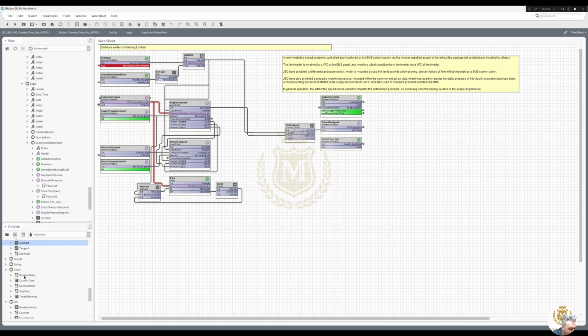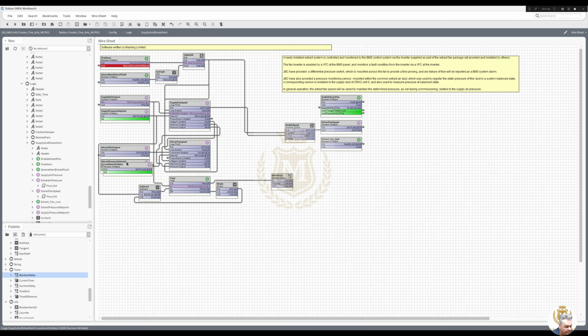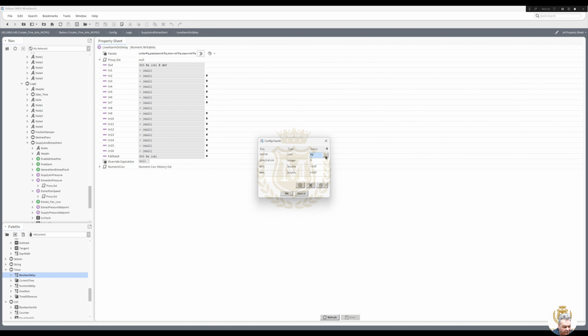Timer, Boolean. Wait 5 mins. In. I presume we probably need that delay adjustable. On delay. Take out that. Duplicate that. Alarm, low, alarm, on delay. We're in seconds. Time, seconds.